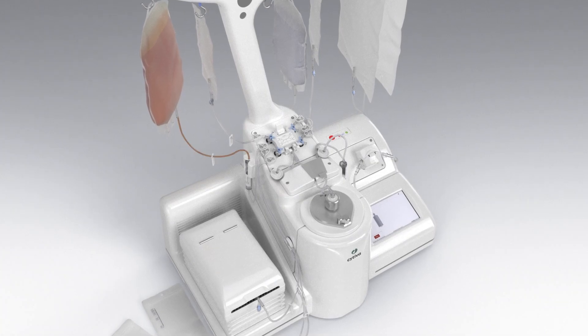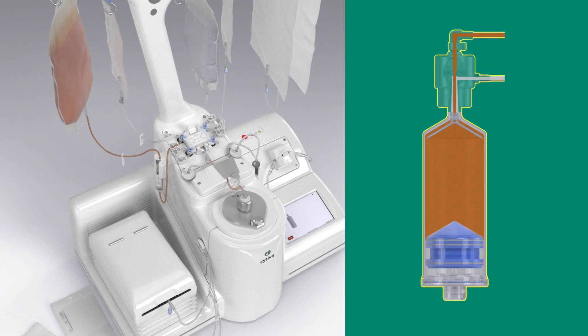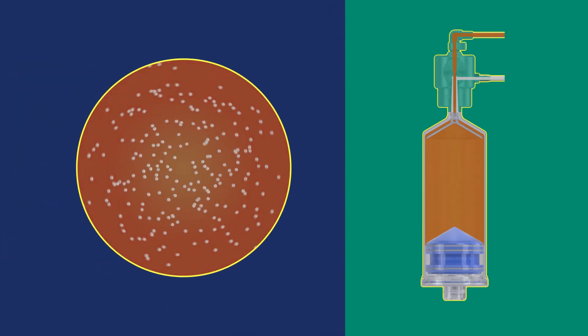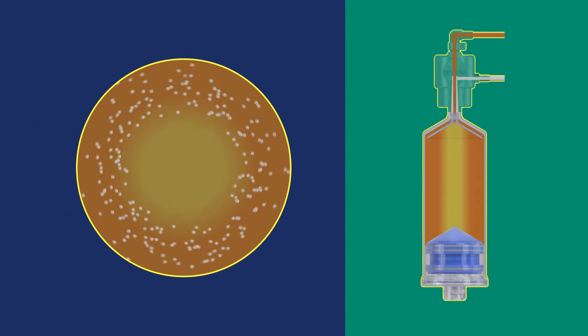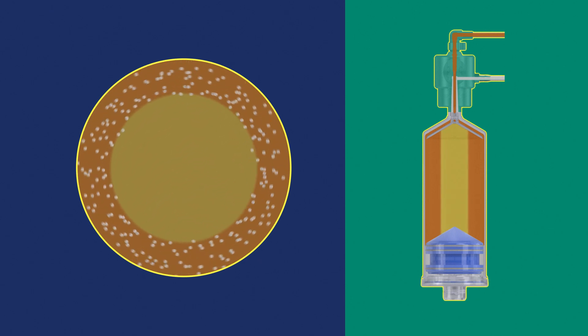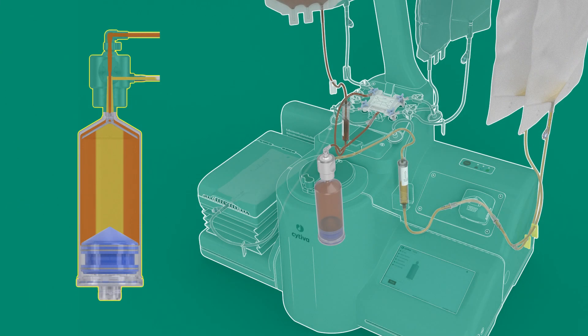Once the chamber is filled, FlexCell centrifuges the cells using your defined parameters. While the centrifugation is running, the continuous flow begins. The peristaltic pump extracts the supernatant from the spinning axis while the initial product continuously fills into the separation chamber.